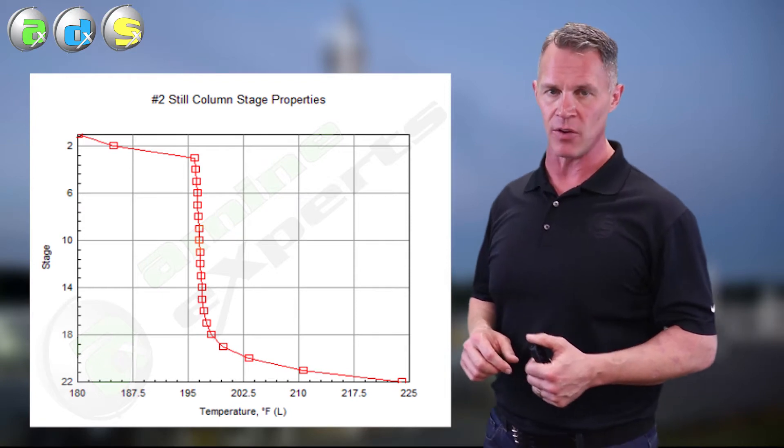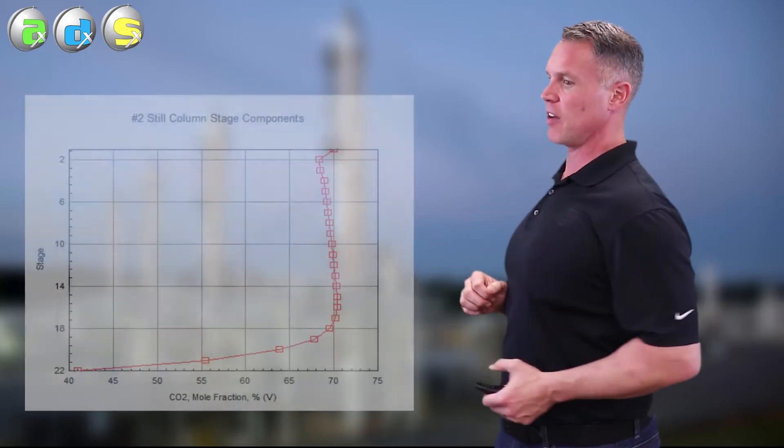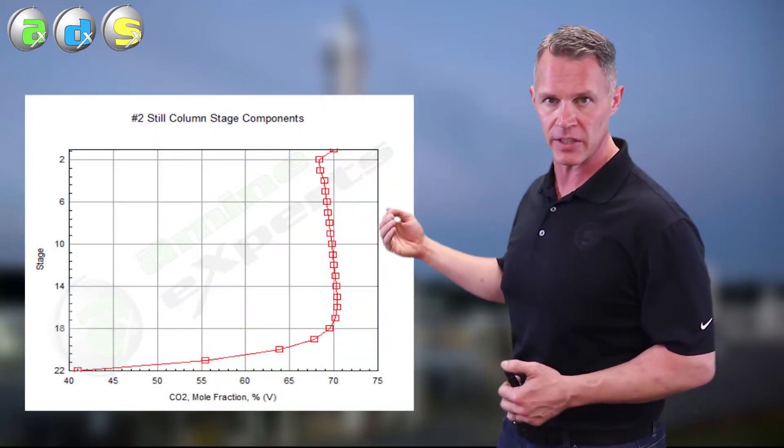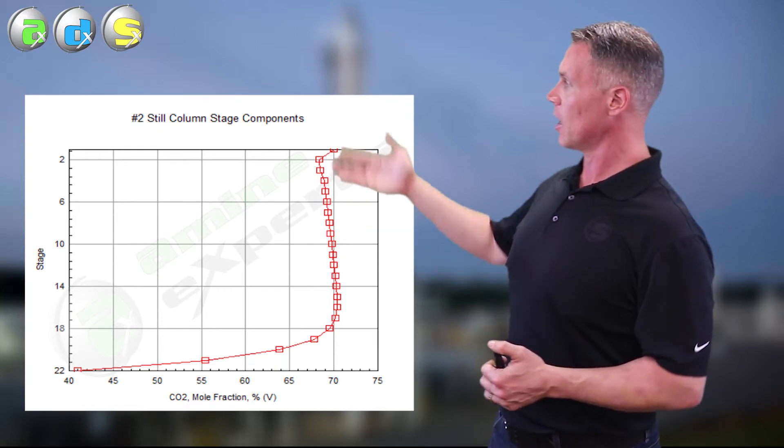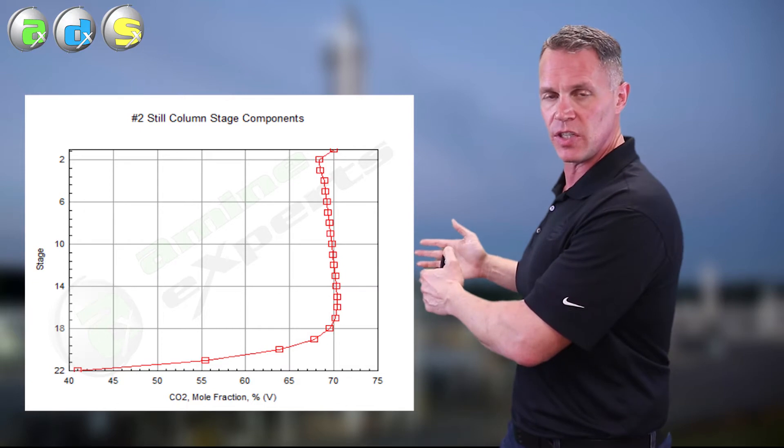It then goes into the reboiler, which finished the job of heating. We were boiling the amine in the reboiler, but we weren't boiling it very hard. And the problem there is, if we look at the corresponding CO2 profile in that regenerator, when we're not heating the amine up, we're also not removing CO2.